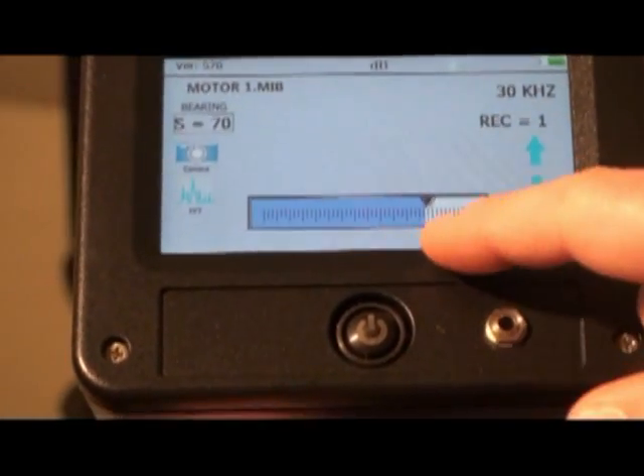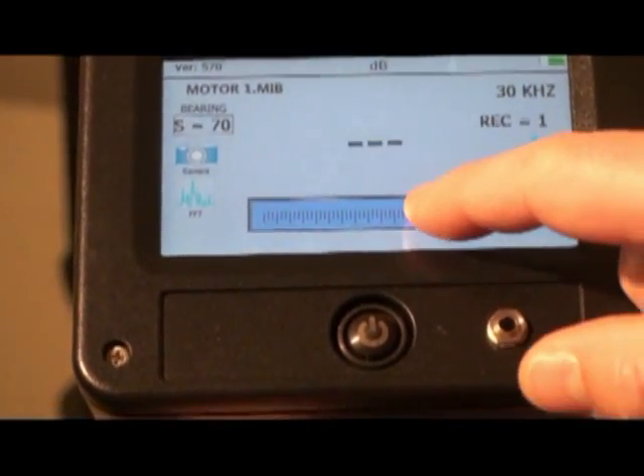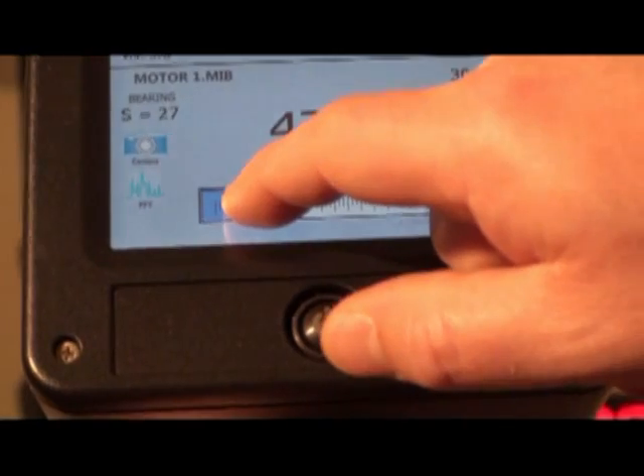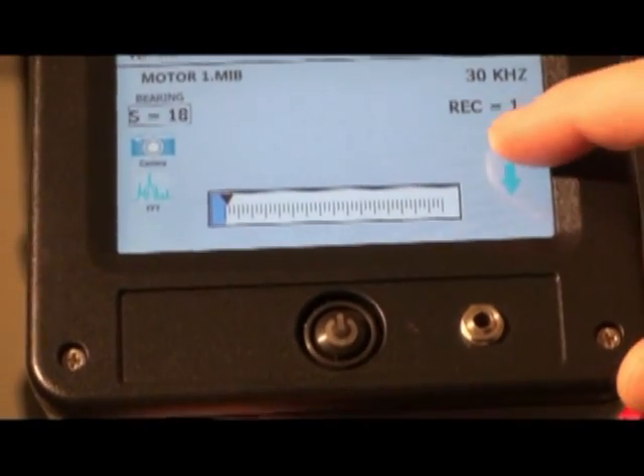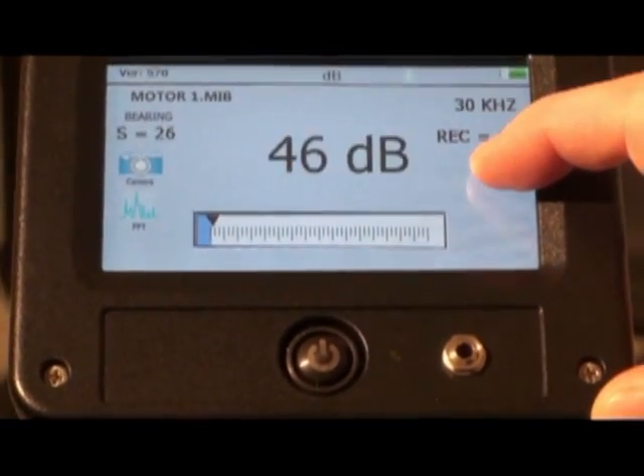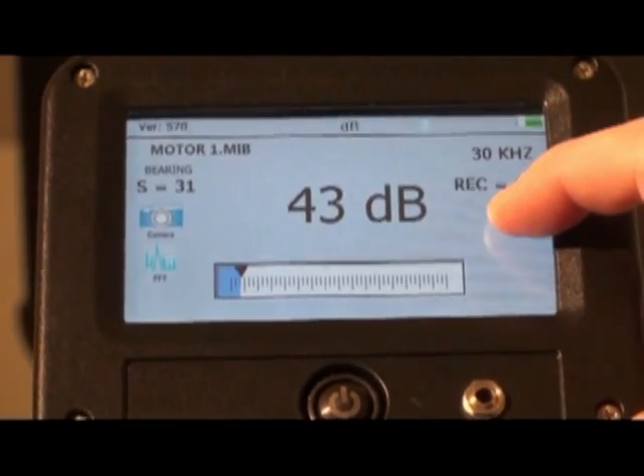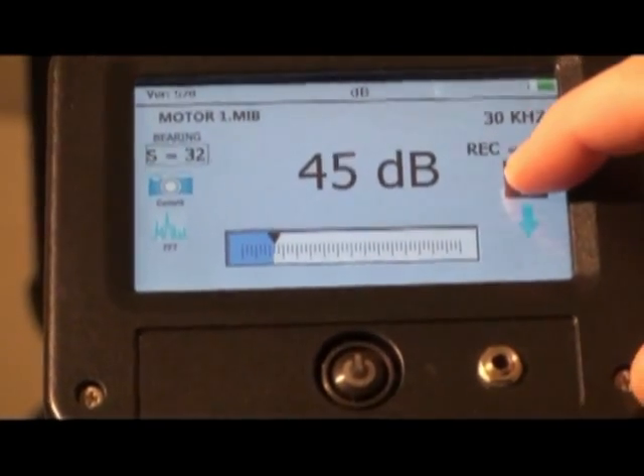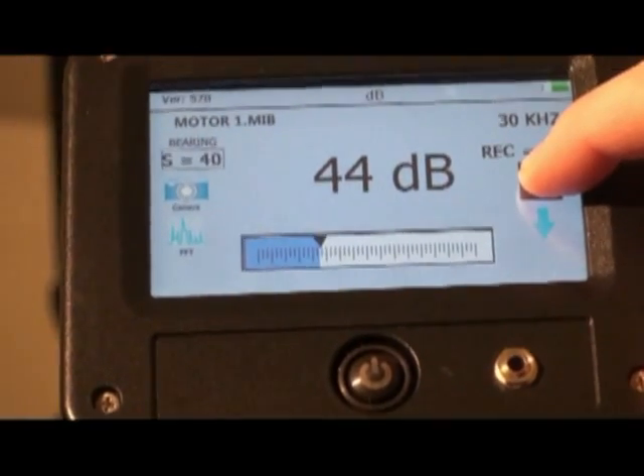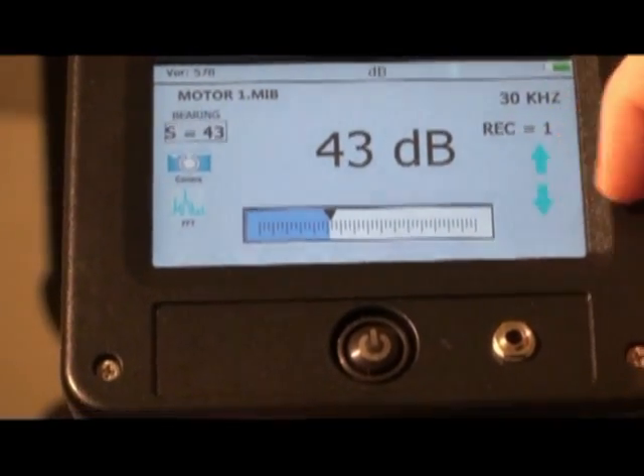To change the sensitivity, touch the S equals box. You can adjust the sensitivity with the up-down arrows, or by touching and sliding the intensity bar graph. For optimum recording, adjust the intensity until the bar graph is at or about 30% of scale.